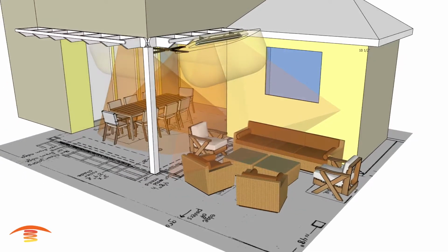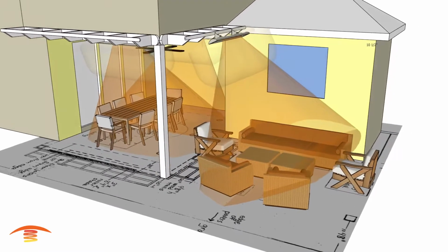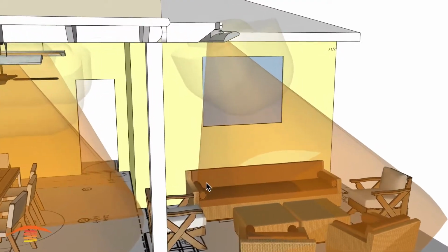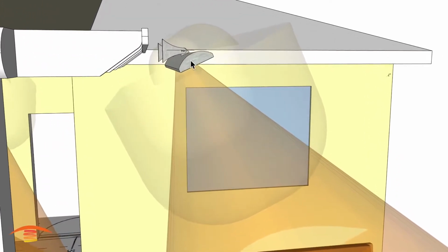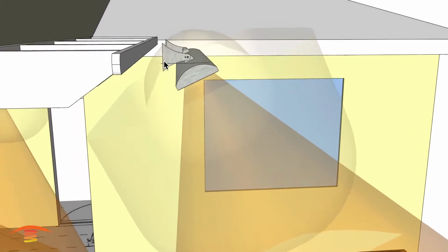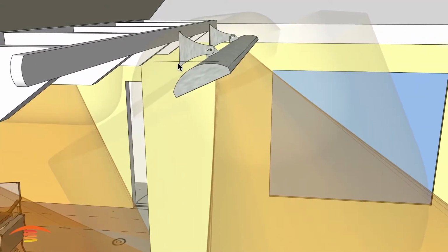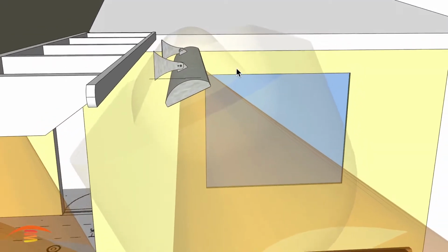All right, so that would be the one option, the first one was a Slimline, and this would be the CD 6024 option. Here you're getting a lot better heat coverage in at least this space and this space. Again, you can't really get that angle down without compromising the clearance here. You would have to come up with some way of engaging the bracket to this piece here. And obviously the bracket itself is a lot longer or taller, and you'd have to get the extended bracket as well for this application.